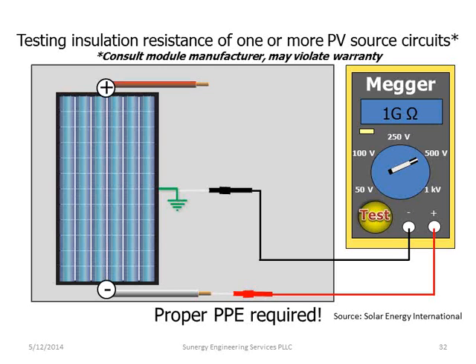It should be fine. Actually, I take that back. There is a potential issue. I've never heard of any failures when I've talked to anybody about it, but it is a concern. If we did have a short on this guy, say we had a positive short right back to ground, and we did this at 1,000 volts, then we could be subjecting a module that's rated at 600 volts to 1,000 volts. And if there was a bad diode or there was a shading issue where a diode was being fired, you could potentially damage the diode, because the diodes are rated at about 45 volts.